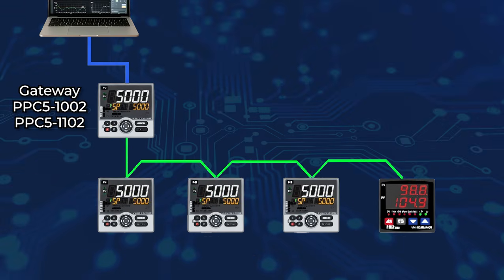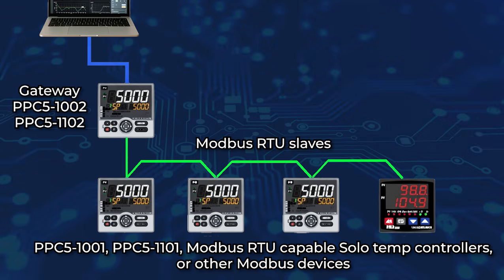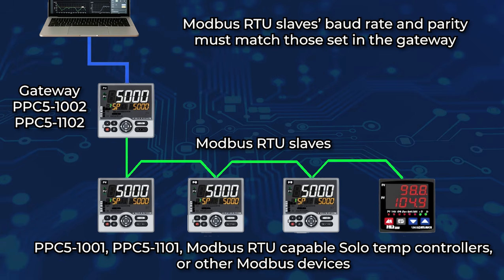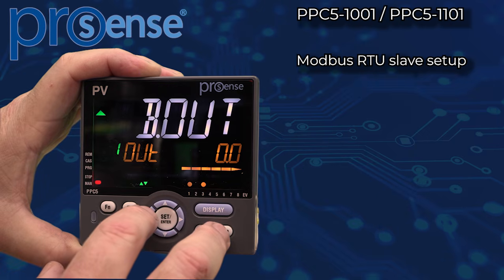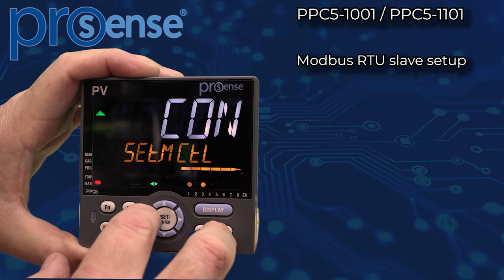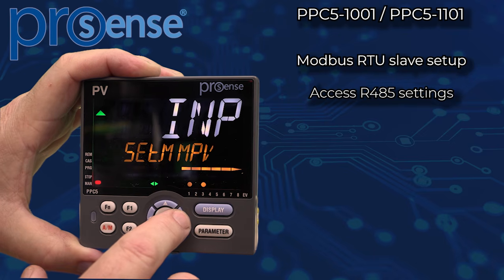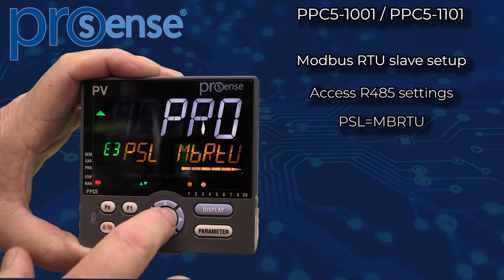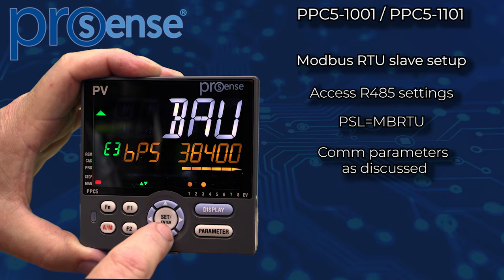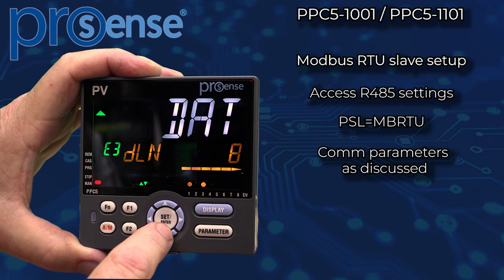All serial devices that will act as Modbus slaves to the gateway must have their baud rate and parity parameters set to match, and must have their data bits set to 8 and stop bits set to 1. To set up a PPC5 as a Modbus slave in a network like this, access the RS-485 menu. Make sure Modbus RTU is selected in the protocol selection parameter. Set the other parameters as we've just outlined.